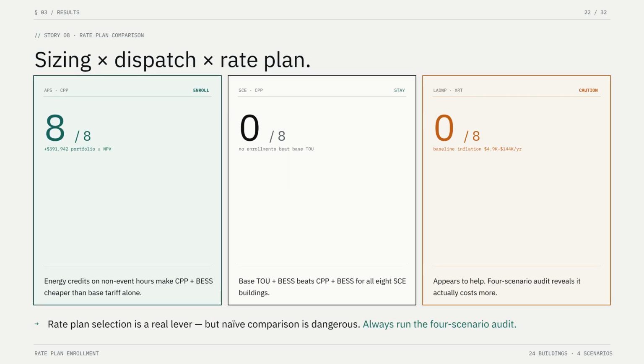Story 8 adds a third dimension, rate plan selection. We tested 24 buildings against their utility's alternative tariff. APS's critical peak pricing adds $591,000 in portfolio NPV, so all 8 APS buildings should enroll. SCE's CPP doesn't beat the base time of use plus BESS for a single building. And LADWP's experimental rate XRT is a cautionary tale. A naive comparison made it look beneficial, but only because it inflated the baseline. A 4-scenario audit reveals it actually costs more. The method generalizes.